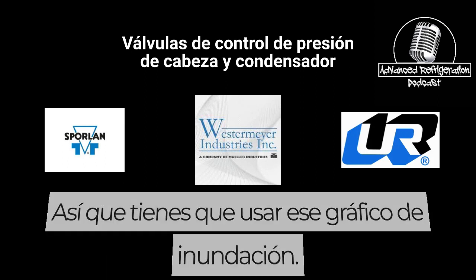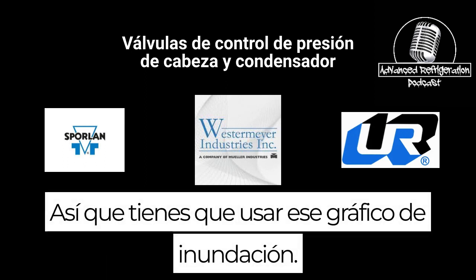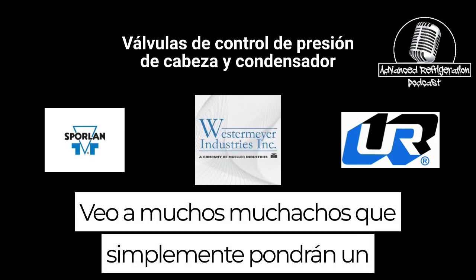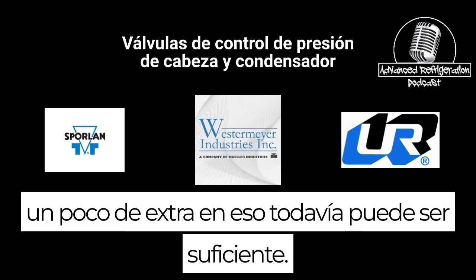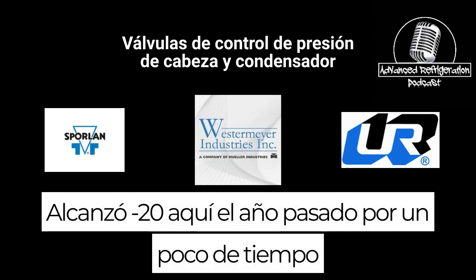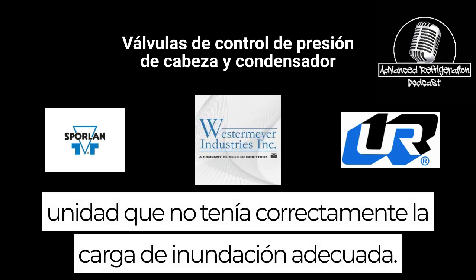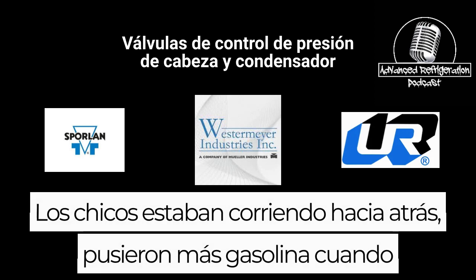So you have to use that flooding chart. I see a lot of guys that'll just put a little bit of extra in, and that still may not be enough. It hit minus 20 here last year for a little bit. Any unit that didn't have the proper flooding charge in it, guys were running back to put in more gas.